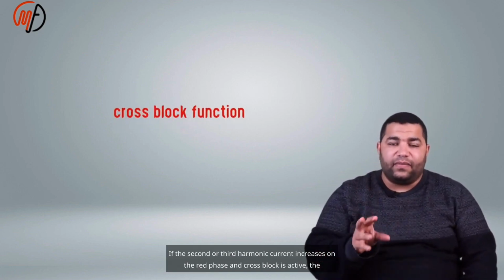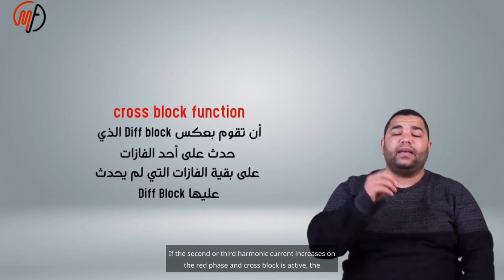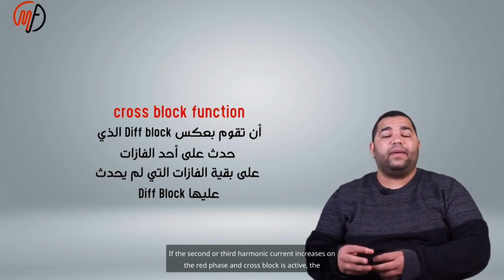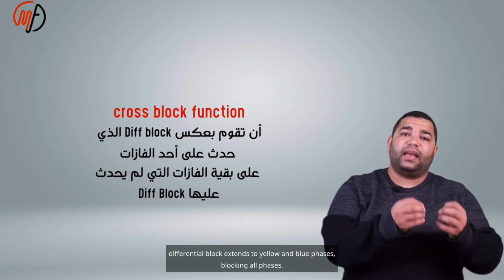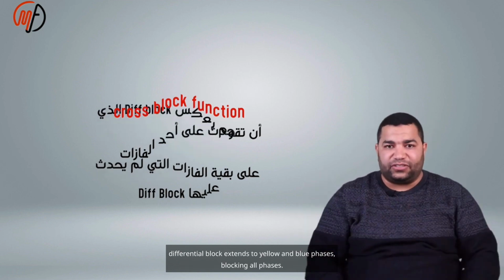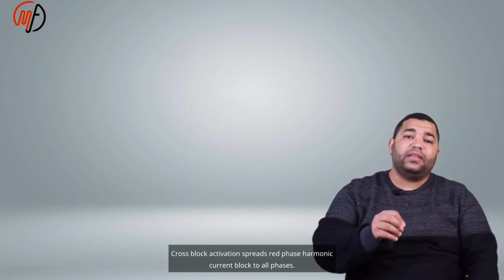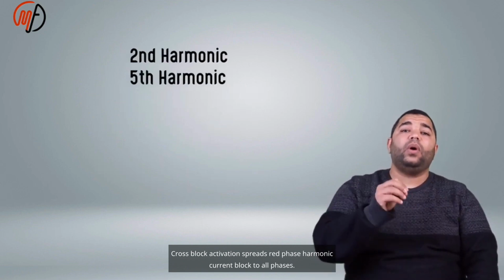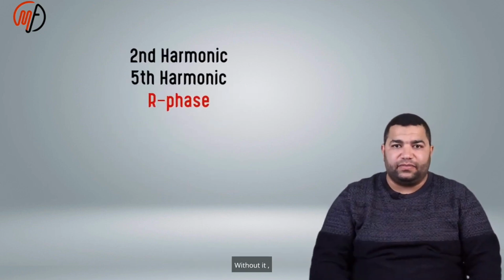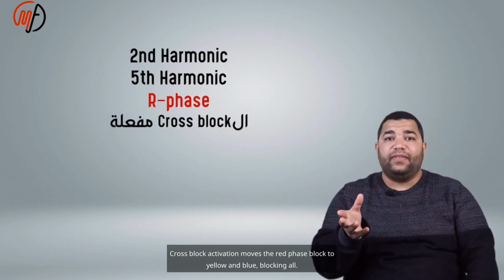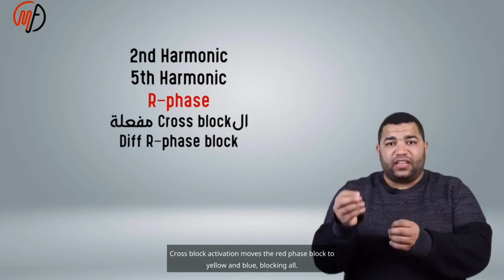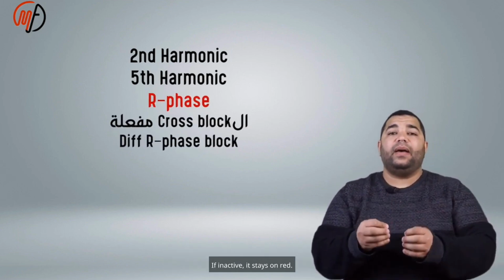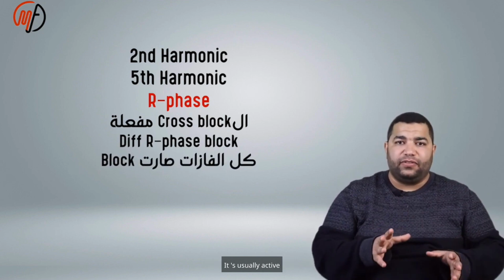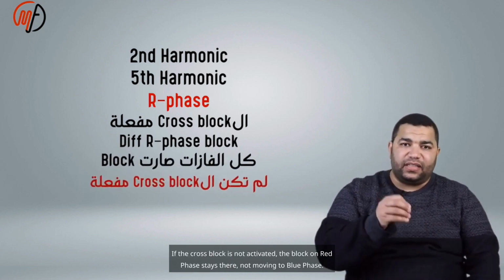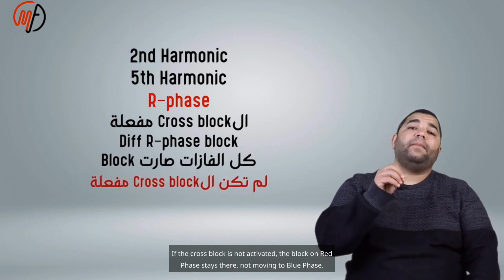If the second or fifth harmonic current increases on the red phase and cross-block is active, the differential block extends to the yellow and blue phases, blocking all phases. Cross-block activation spreads the red phase harmonic block to all phases. If it is inactive, the block stays on red. It's usually active. If the cross-block is not activated, the block on the red phase stays there.